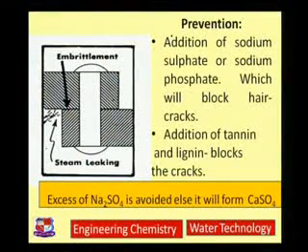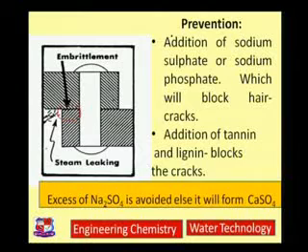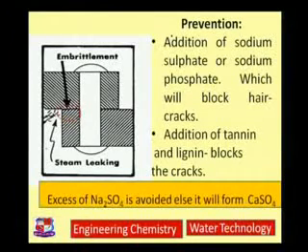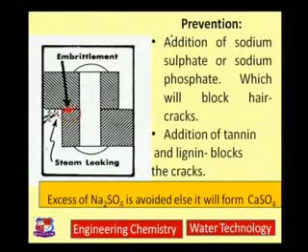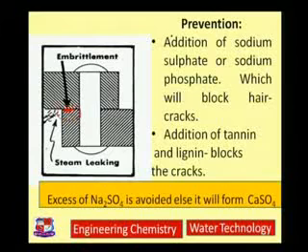Here you can see cracks from where steam is leaking and embrittlement has occurred — the boiler material is removed or dissolved in the form of sodium ferroate. This is nothing but alkaline corrosion of the boiler material.